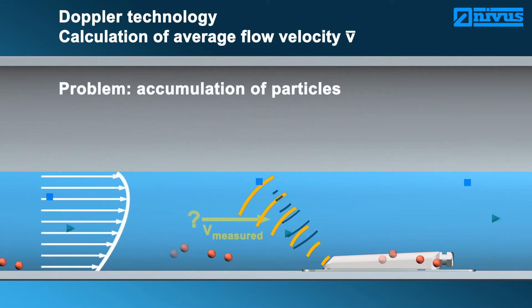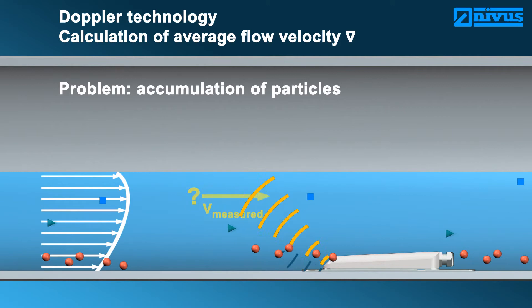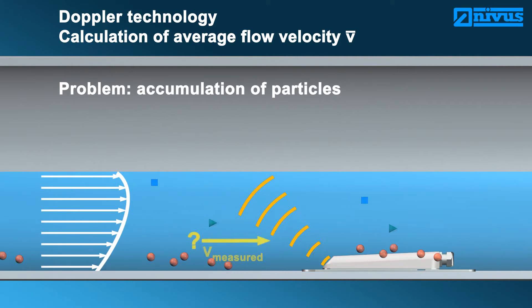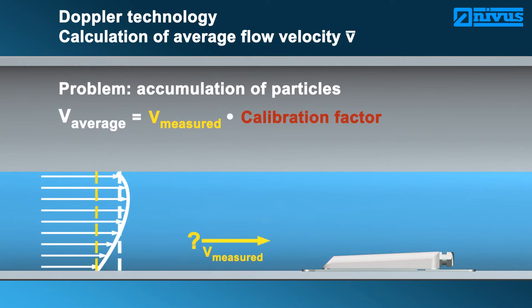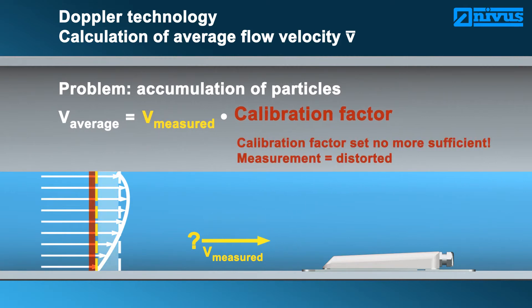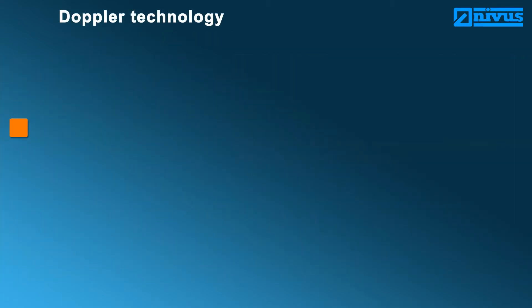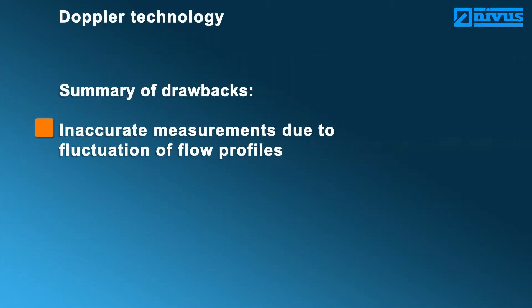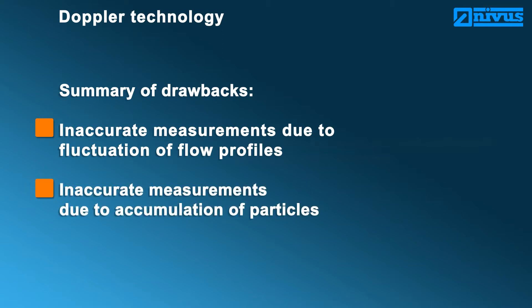Accumulation of particles generates a stronger measurement signal and hence is determined by the sensor as the measurement spot. A local variation therefore creates a distorted reading which varies from the calibration. The shortcomings of Doppler measurement systems in brief: faulty results at varying flow profiles, faulty results in case of changing particle concentration, and no permanent calibration possible.